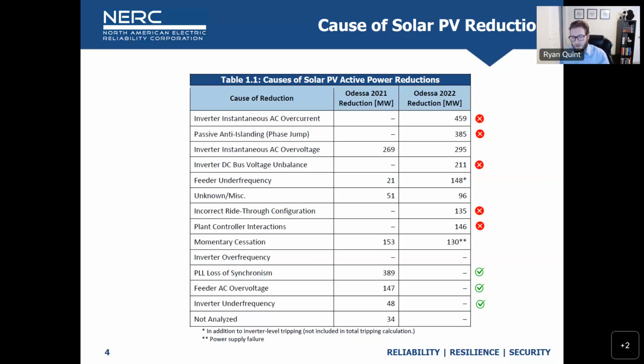I think that's a critical piece of the puzzle too, because in most of these events, when we show up to the asset owner and say, hey, we'd like to have a call with you to talk about what we saw, a lot of folks are not aware that anything had happened, because the inverters will automatically reconnect 5 to 7 minutes later and back to business as usual. They don't really grasp that we had 15, 20 other plants all do exactly the same thing, and this is a fairly big reliability risk. So that new proposed standard could go a long way in helping shore up these types of issues before they boil up to really big reliability risks.